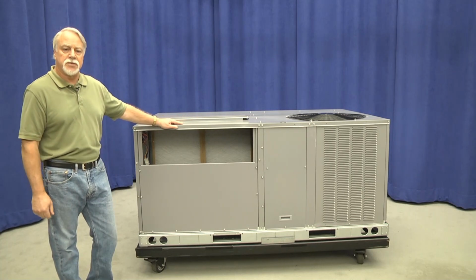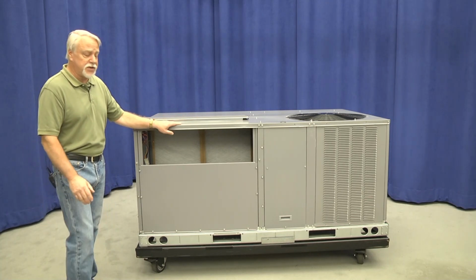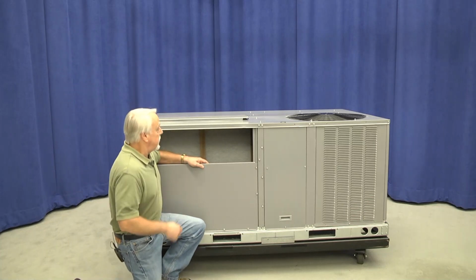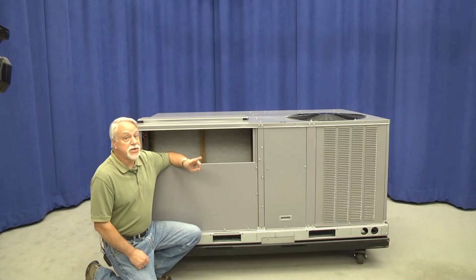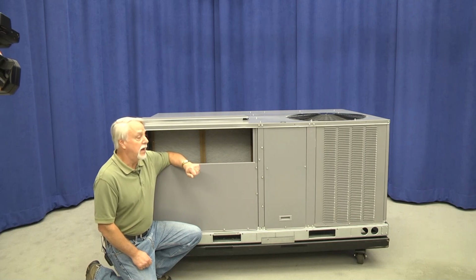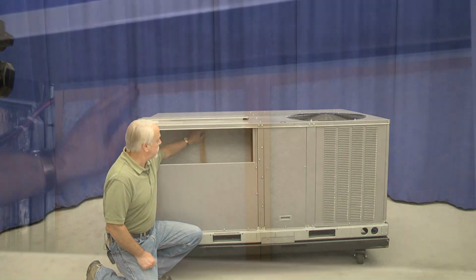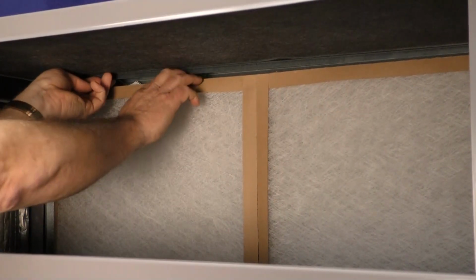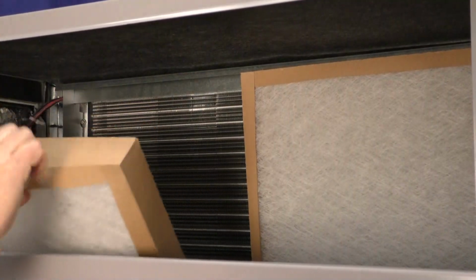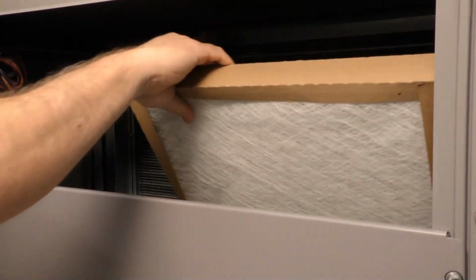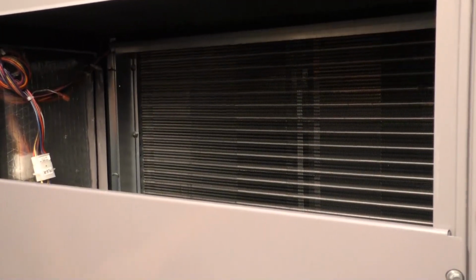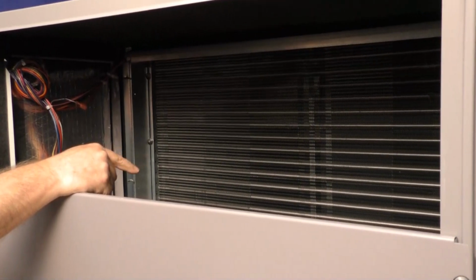The standard filters for this machine are the 2-inch, 10% efficient throwaway filters. Accessing those, there's still 2 in this particular chassis size. We still have that hinged rail at the top of the filter rack that allows these filters to be pivoted forward and removed from the unit for easy service. With the removal of both of these filters, this allows us access for cleaning of the evaporator coil. It also allows us inspection of the condensate pan just below the evaporator coil.